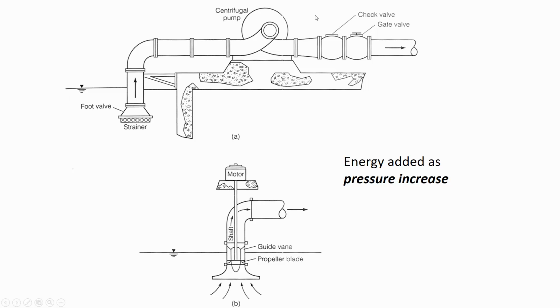In a pump like this, you'll generally try to minimize the height difference between the water surface and the pump, because that delta Z can cause or contribute to cavitation, and so can a really long length on the suction side, because there are head losses. Any head losses that occur in the suction side of the pump may contribute to cavitation. How to assess the threat of cavitation is something that we'll do in our second example today.